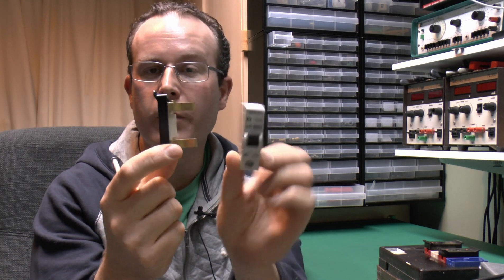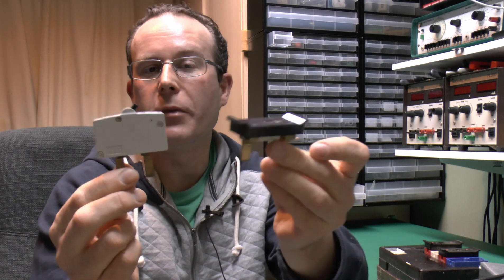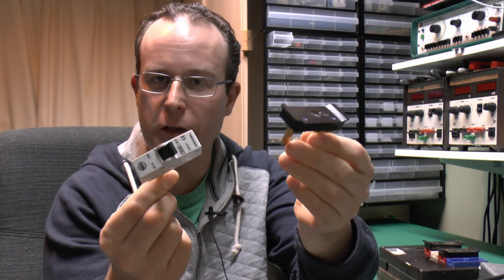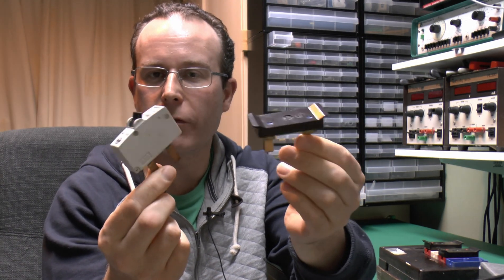So if you have some of these and you were thinking about buying a load of these to replace them, simply don't bother. It's a waste of time and money. These circuit breakers only do the same purpose as these things do. The only difference being that these can be reset very easily whereas of course these old fuses, it's a bit of a bother to get the old fuse wire out and re-wire it in there. But of course if fuses are blowing all the time then clearly there's a major problem with the installation. It doesn't matter what you've replaced it with, the problem is still going to be there. It's not going to go away and it's probably going to get much worse.